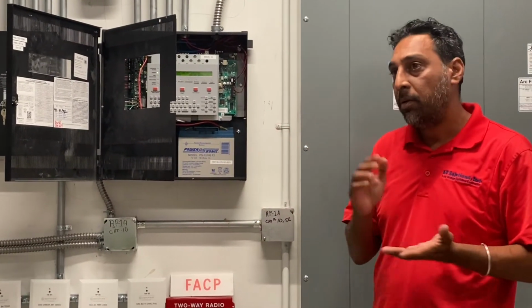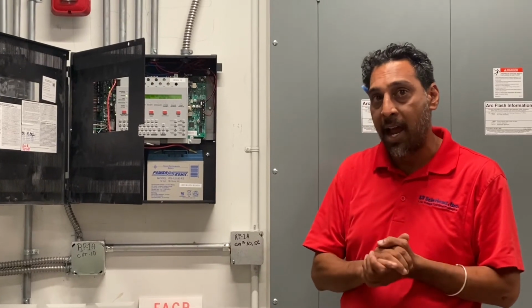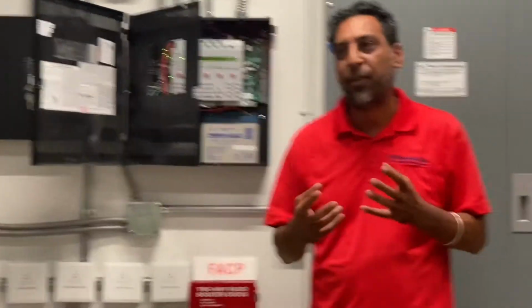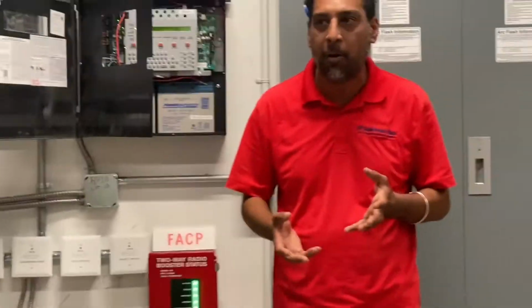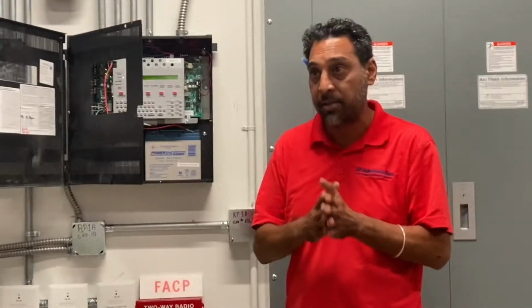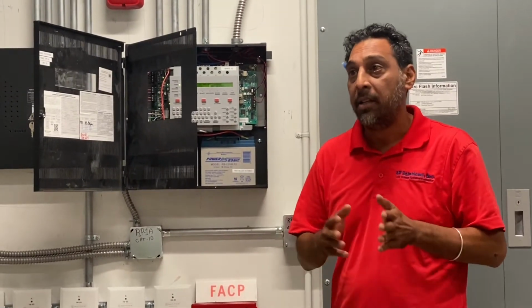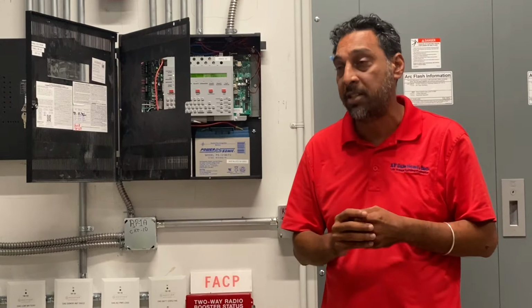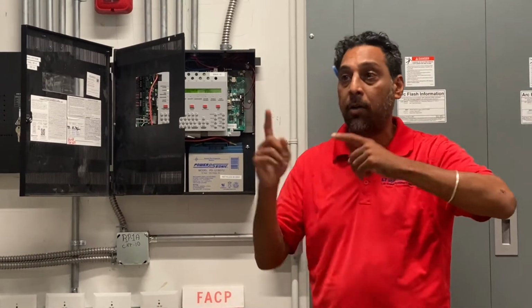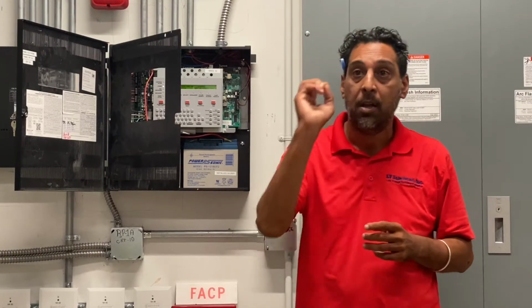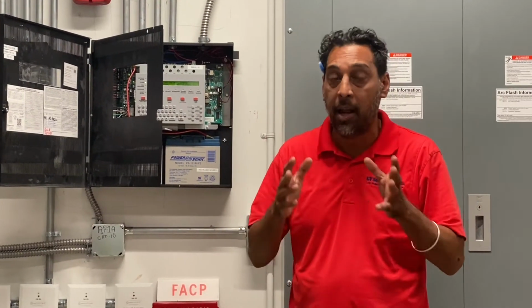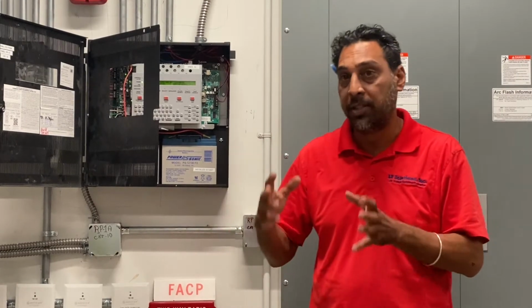Okay? Now, your non-latching supervisories are your tamper switches where they shut the water off of the sprinkler system, your main water valve outside for the backflow. Those are what we call non-latching or track supervisories. Typically that will come in if your sprinkler guy's working on the system, he shuts the water off and the panel will automatically track supervisory. That's something you don't have to reset. It's to protect you guys, to let you know someone shut the water off to the building. If it says backflow, or your risers, once again, the description will tell you exactly where it is.